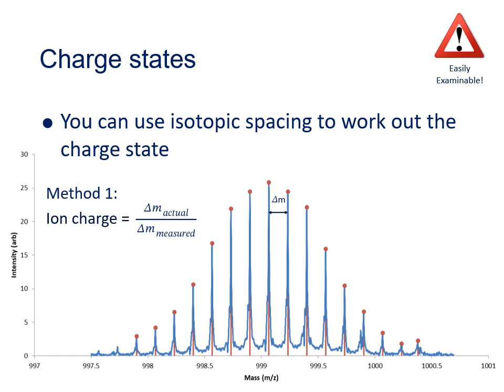There are several different methods you can use to work out the charge state of an ion. In this example we're lucky, we can see the isotopic distribution. In an isotopic distribution, the mass spacing between the peaks should be approximately 1 Dalton. And if the ion is singly charged they will be. But if the ion is doubly charged, that mass spacing between isotopologues will be half a Dalton. If it's triply charged, a third of a Dalton, quadruply charged, a quarter of a Dalton, and so on. So we can estimate the charge state of the ion by dividing the actual mass difference between isotopologue peaks by the measured mass difference between isotopologue peaks. It's always a good idea to measure the charge across multiple isotopic spacings rather than just between one pair of peaks.